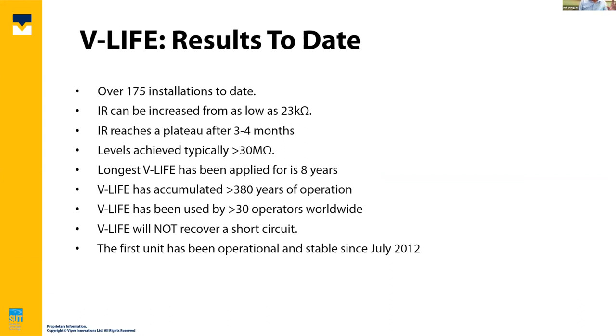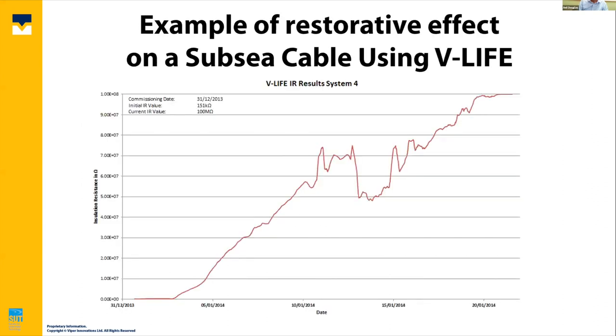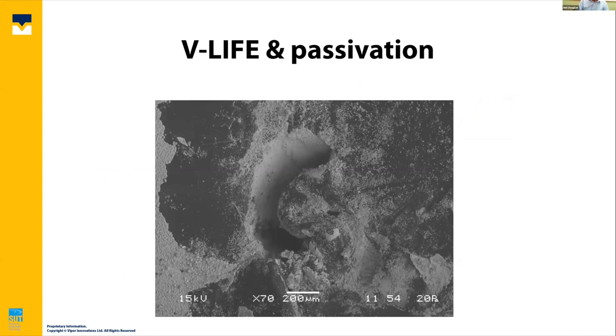Just typically, some data. We've had over 175 installations to date. With the insulation resistance down to about 20 kilo ohms, we're relatively confident we can recover your system. Below this 20, 23 kilo ohm figure, it becomes a lot less likely that we can get enough energy in to get the system working. Typically, we'd expect to get you up above 30 mega ohms. As you can see there, we've got 30 different operators as our clients, and we've accumulated over 380 years of operational experience with V-Life. And right at the bottom, the first unit has been operational and stable since 2012.